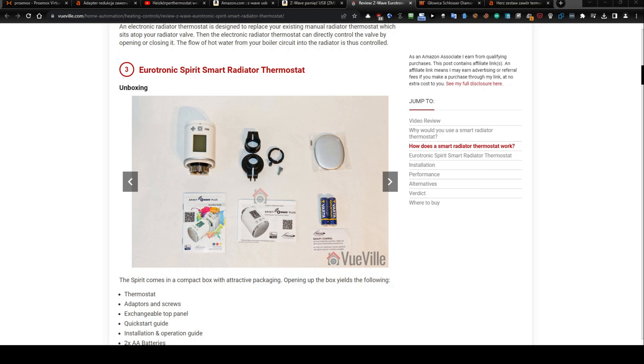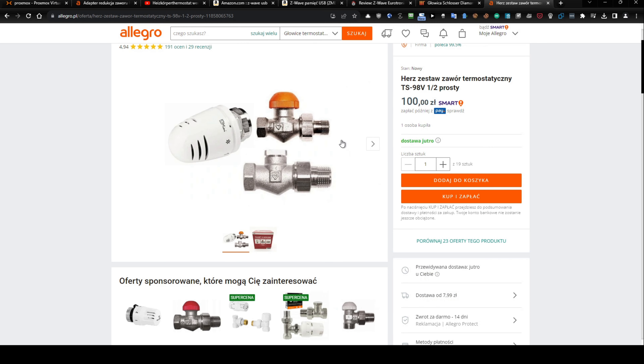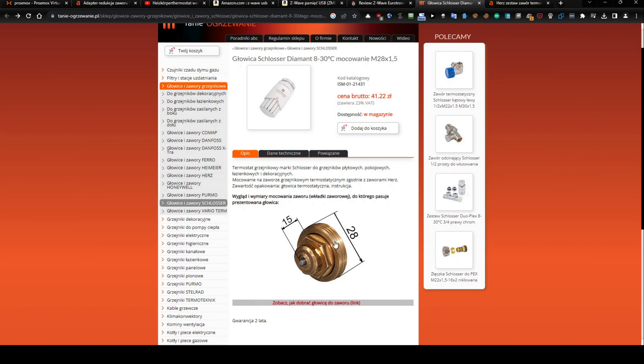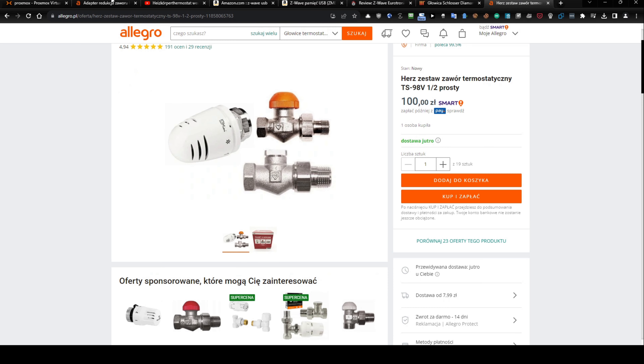You can see three black adapters here. In my case there is a problem because I have an inner valve from Herz, exactly this one. The inner valve is 28 millimeters diameter, and there is a problem because most modern thermostats have exactly 30 millimeters diameter. I decided to look for a solution, because the building administration doesn't allow replacing this set with something different — for example a Danfoss set — because I would lose the warranty. In case of any failure or damage, they will not pay or fix the problem.